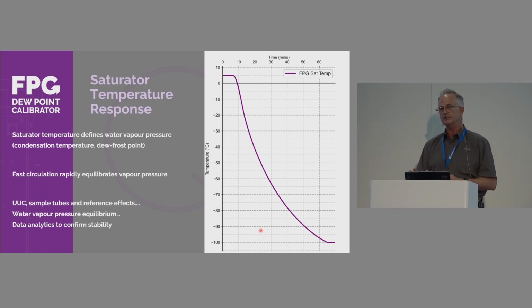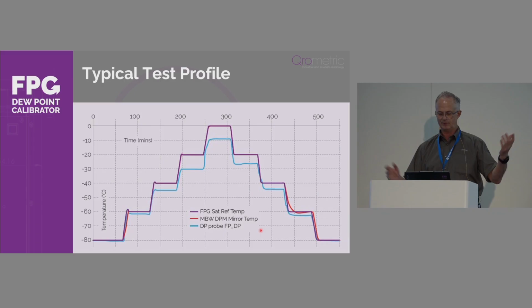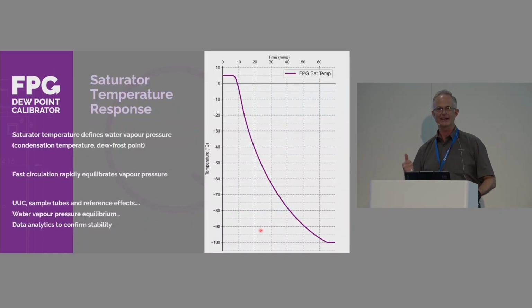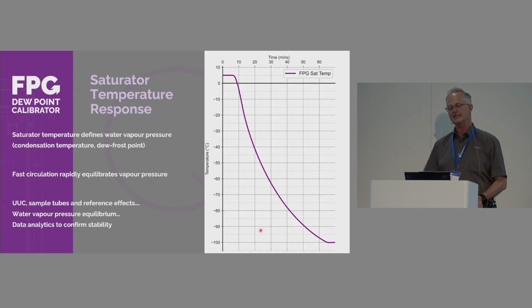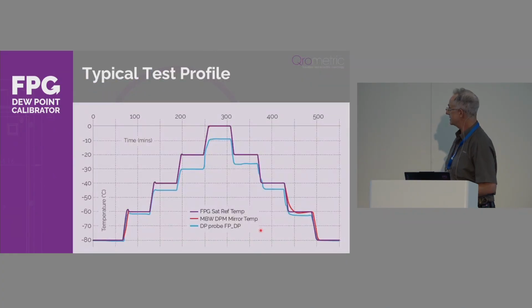That doesn't mean you're ready to calibrate in an hour, because the sensors and the devices all have to equilibrate to the vapor pressure. So now you know what's coming next, right? It's like magic. But that's a typical response setup time. That's a typical test profile.